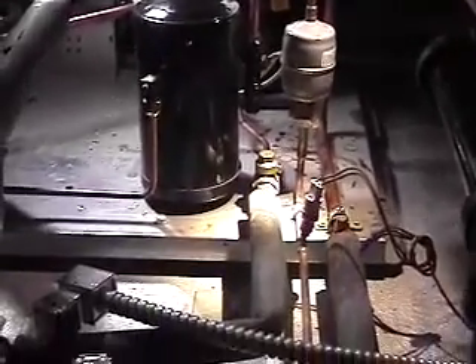Okay. It resets, so it'll go off at 275, and it resets at 190. So you can lose water 15 or 20 minutes, it comes back on, it'll reset, except for the fact that it will be logged on the log. You'll know, you'll be the wiser. This is going down to that panel now. Yeah, it goes down to our control. Right? It goes down to our control.